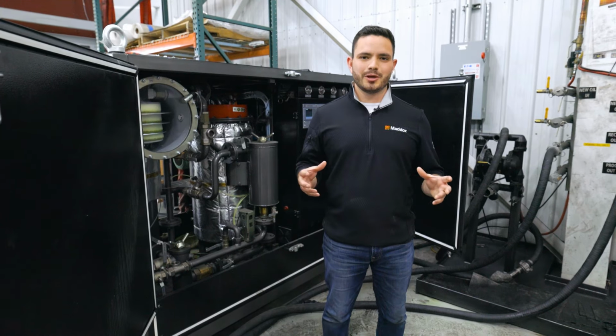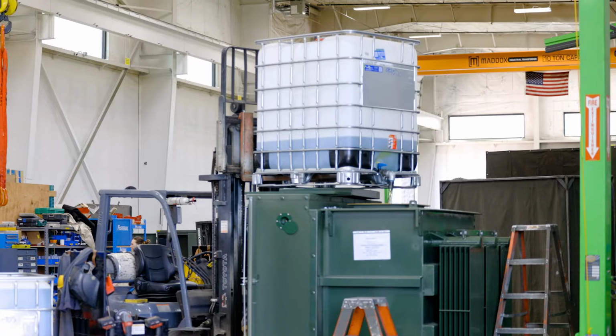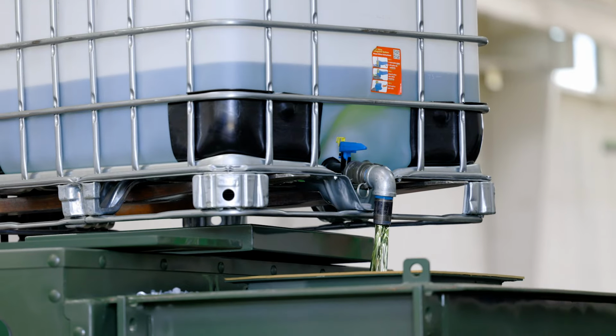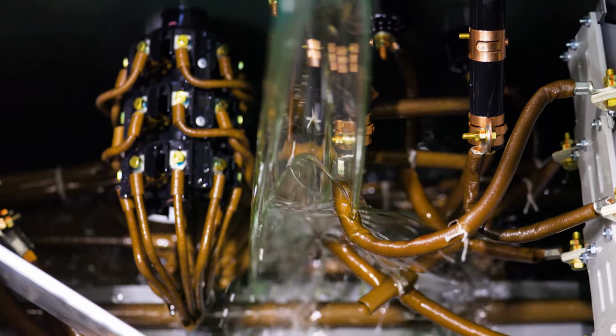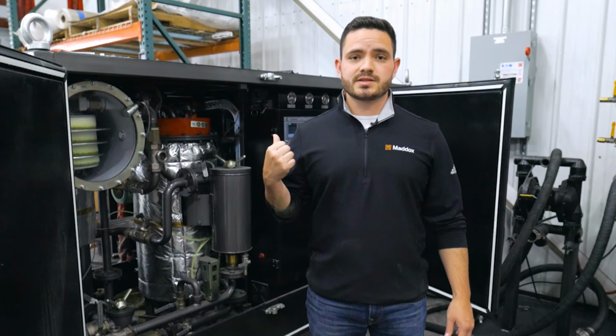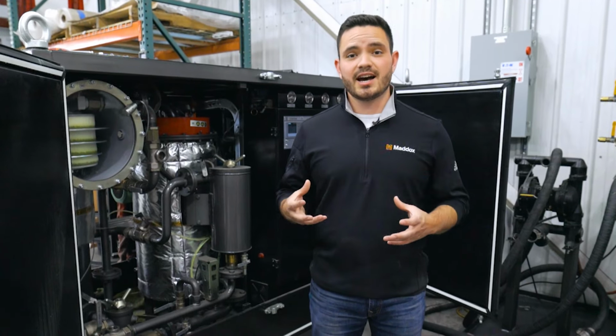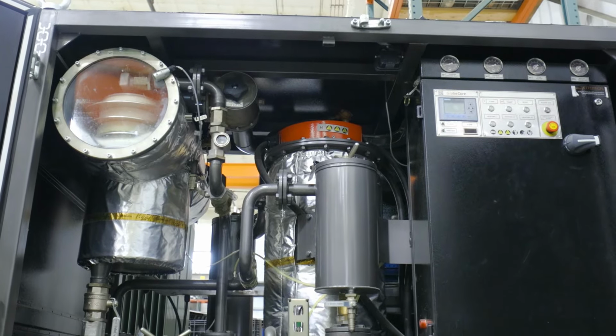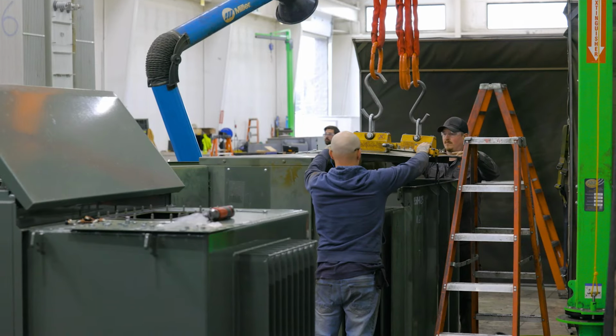Next, we'll replace the fluid. We'll either use all new fluid or the original fluid depending on its condition. If the incoming DGA results show a buildup of gases or moisture, we'll run it through our processing unit, which is a degasser and dehydrator, and we'll process it before we reuse it. Lastly, we put the lid back on.